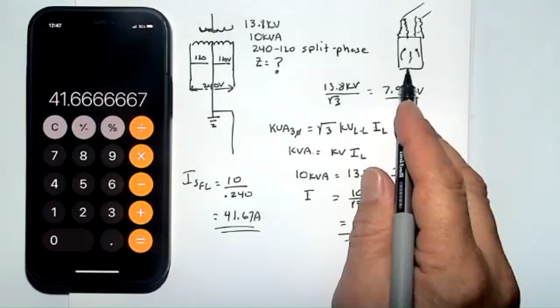Now, as far as the fault current, let's take that number, 42 amps, and divide that by our impedance. What is our impedance for this kind of transformer? I said it earlier, it's going to be between 2 and 3%. I think the one we showed was 2.4%. So take that number divided by 0.024, and we get 1736 amps. Typically in our homes, we're using 10 kA breakers, so this is well within that range.